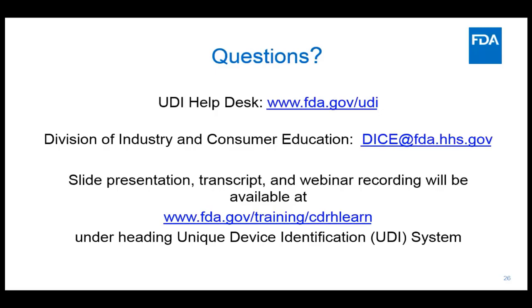If you were including an alcohol wipe, there might be a question of whether it's a combination product or not. So there are considerations such as that. You also mentioned there were things in the package that were not devices at all. We sometimes get questions about this, like if somebody has an electrode prep kit with two or more medical devices and they otherwise meet the definition of a convenience kit, but then they also include a razor blade for shaving or something like that. Just to be clear, we don't expect a UDI to be assigned to any non-device items. The requirement applies to medical devices.